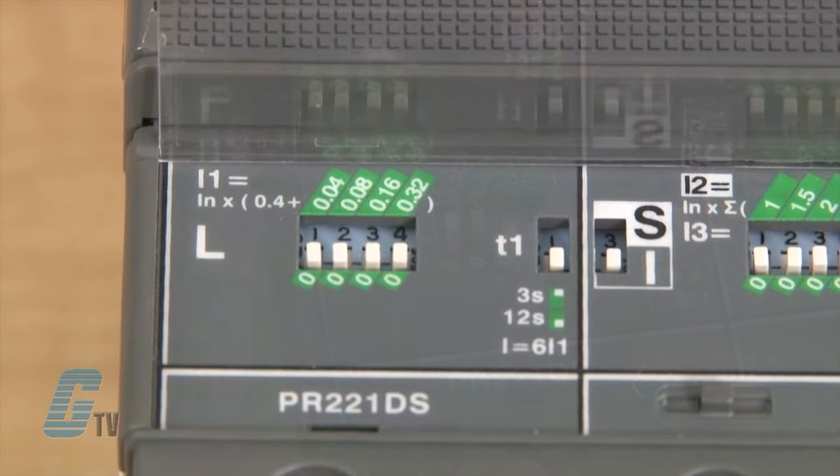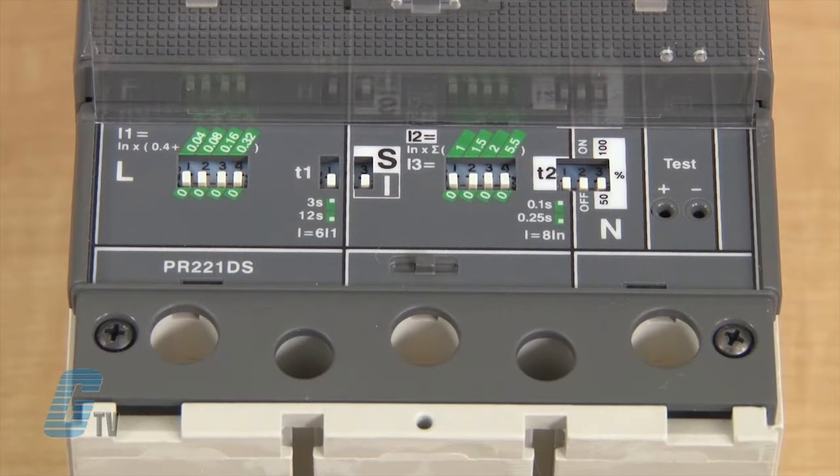I can also set the trip curve time delay with the T1 dip switch here. My next set of dip switches is for setting either a short time delay with S or an instantaneous time delay with I.